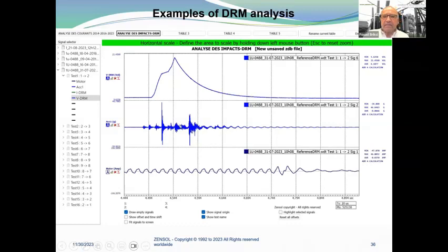So with this, when you do an offline test, you learn what the vibroacoustic signal is. After that, you just have to do your test online, and you just use the motor current and the vibroacoustic only, without the dynamic resistance. Because during this process, you have learned what your vibroacoustic signals are and what impact is valuable.